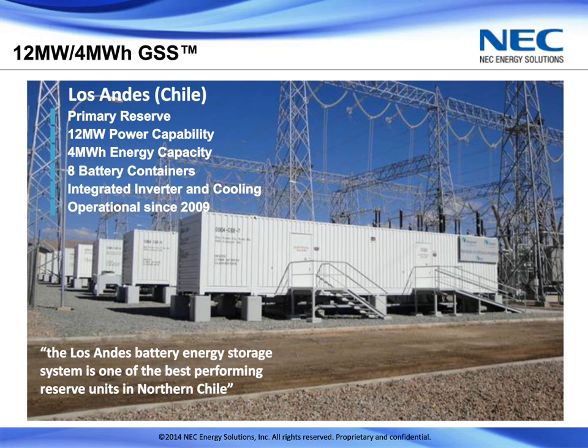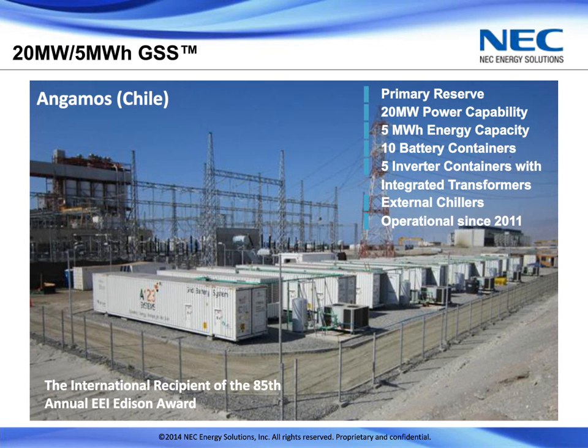Now that first installation was so successful that a second installation was put in place, this time down by the coast in a location called Angamos in Northern Chile. This one was larger. This was a 20 megawatt, 5 megawatt hour GSS, comprising 10 battery containers and 5 inverter containers, installed about 2 years later in 2011. Both of these systems, again, combined, provide the obligation for frequency response that was previously required of generators. And so those generators are now able to improve their output, to increase their revenues, and ensure an attractive return for their owners. I guess a notable award for this site is that it was a recipient of the EEI Edison Award.